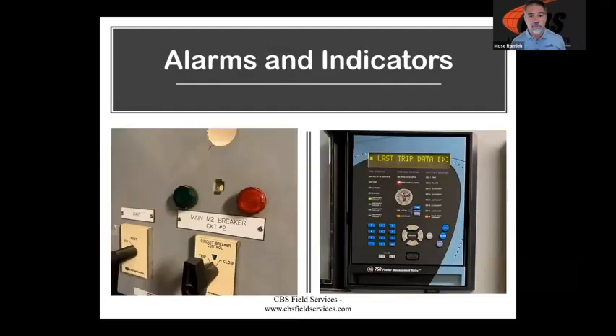All right, a couple of my pet peeves. I hate walking around and seeing that there are no control lights, right? If there are no control lights on our breakers, then one, we don't know the position of them automatically by looking at it. But two, if I don't see a red light burning here, I don't know that breaker has got a good trip coil, right? I don't know that I've got control power to operate that breaker. So it's super important that we keep these lights working.